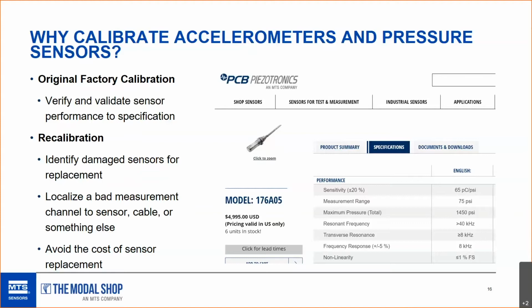And the recalibration is the other event that we have. The purpose of it is to identify sensors that are damaged and need to be replaced, and possibly avoid the replacement of a sensor. If you have a bad channel of the data acquisition, you can avoid that cost by localizing it to the sensor, quite often a cable or something else, right? That's what we're doing in the recalibration event for the sensor.